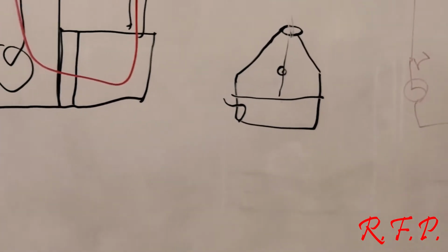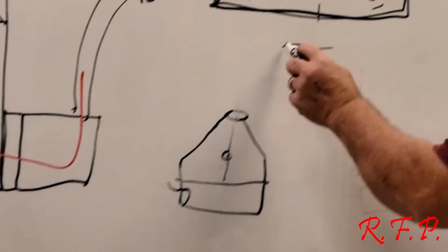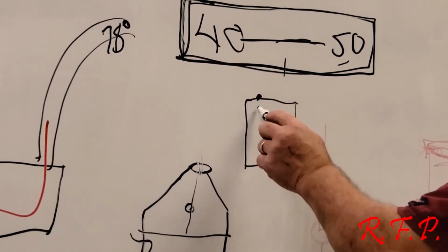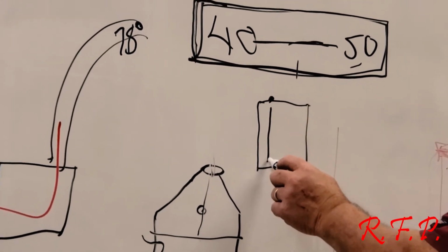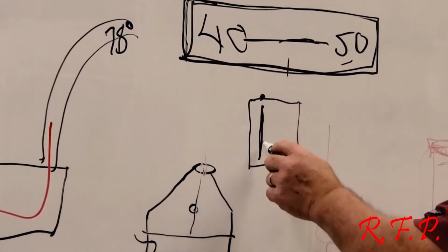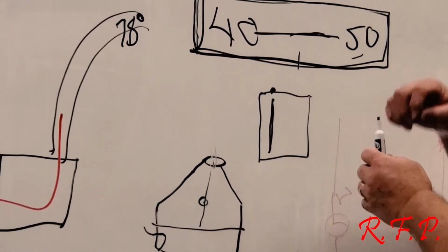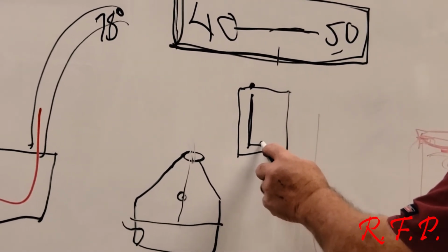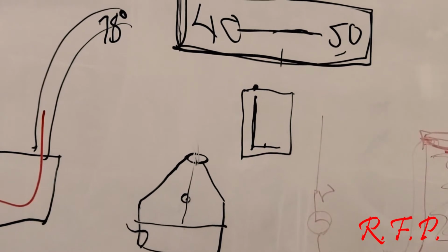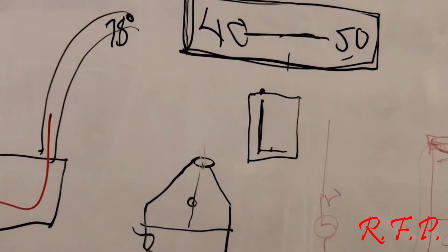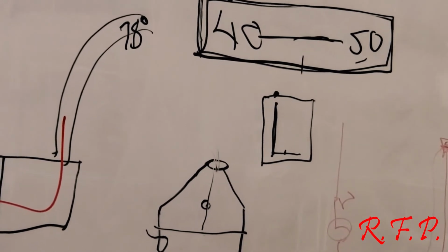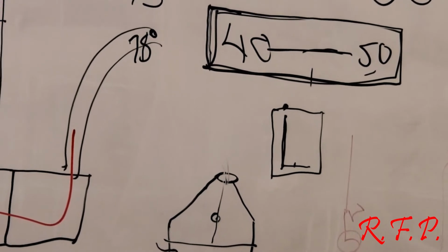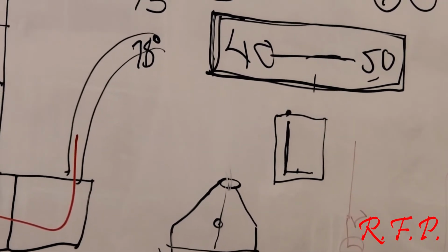But the funny thing about it is the humidistat, if you open it, had a little bitty dial on top of it, and you see this stranded something attached from the dial button, because the dial kind of pulled it up and down, and there's a set of contacts at the bottom, and this is attached to it. It was horsehair. The humidity affects horsehair so that it stretches and lengthens and shortens with different humidity.